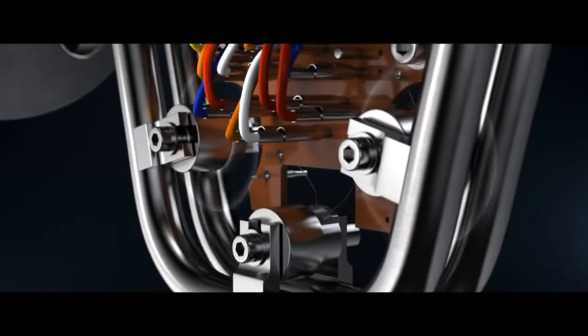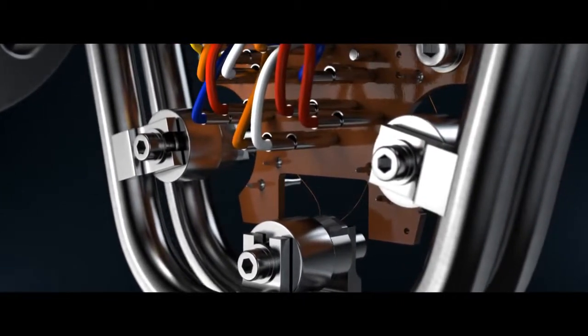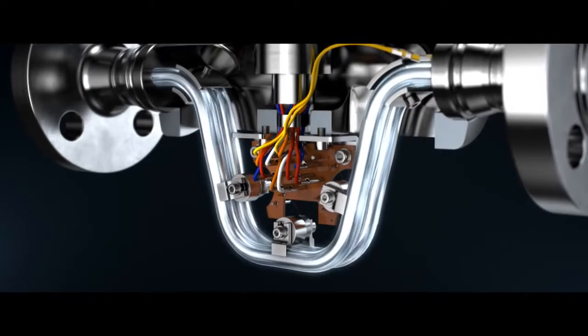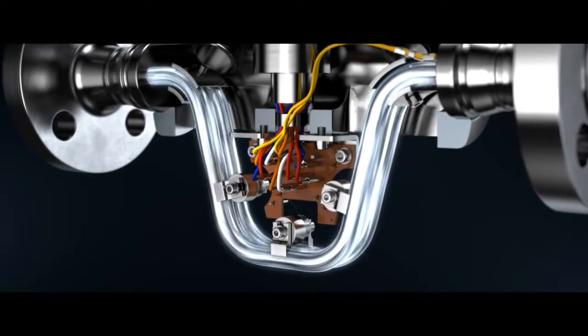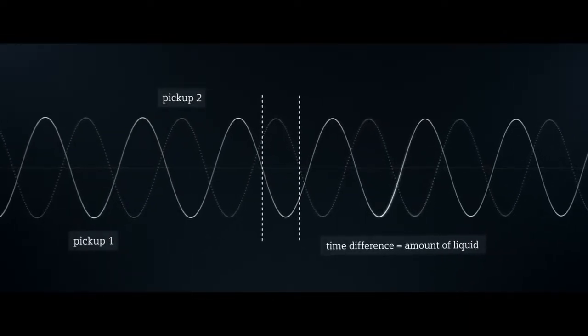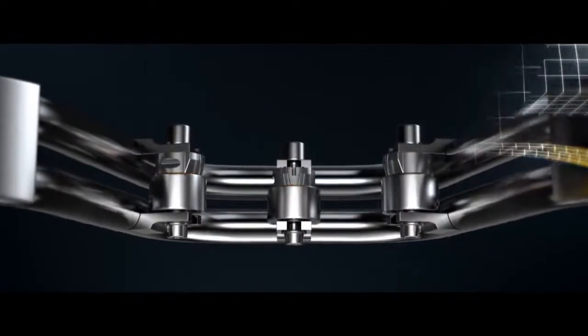The oscillation is measured precisely by two pickups, at the inlet and outlet sections. If liquids or gases now flow through the tubes, a phase shift occurs, as with a water hose. The pickups measure the spatial and temporal displacement. This determines the amount of liquid or gas flowing through the tubes.